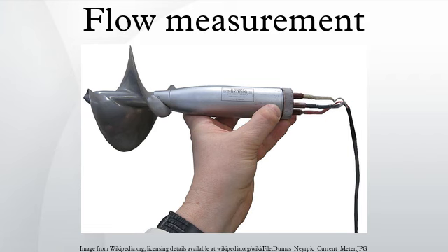The frequency of the transmitted beam is affected by the movement of the particles. This frequency shift can be used to calculate the fluid velocity. For the Doppler principle to work, there must be a high enough density of sonically reflective materials such as solid particles or air bubbles suspended in the fluid.